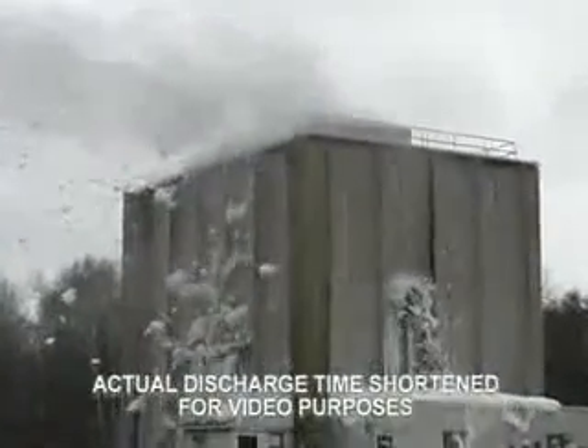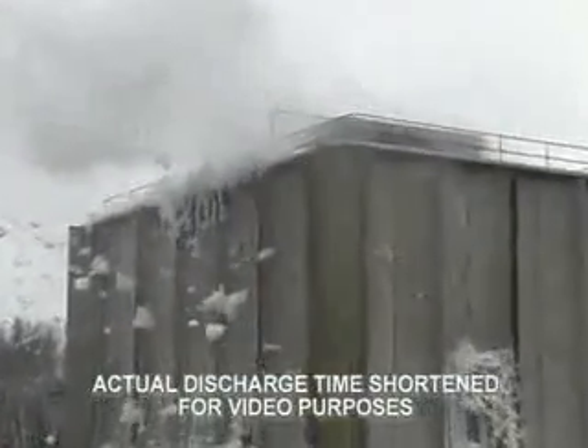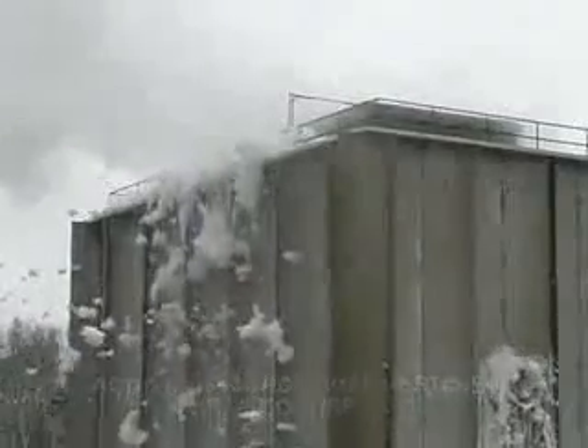Within approximately 3 minutes, the foam has reached its required design level containing the fire. After approximately 9 minutes, the system has totally flooded the building to a level of 50 feet.